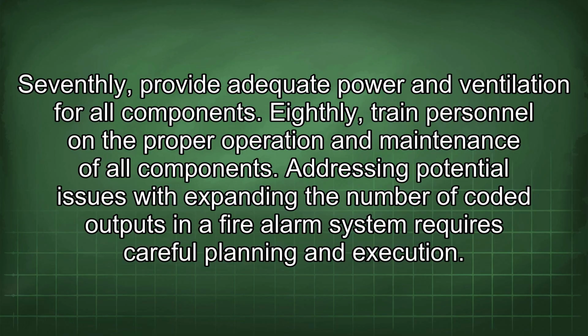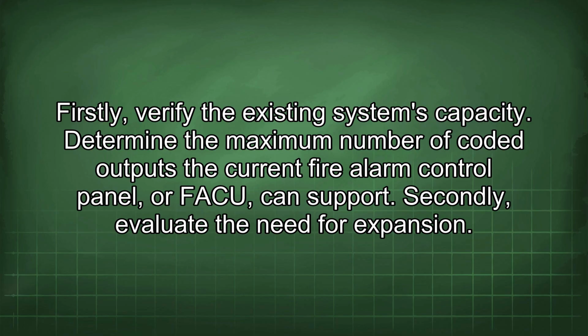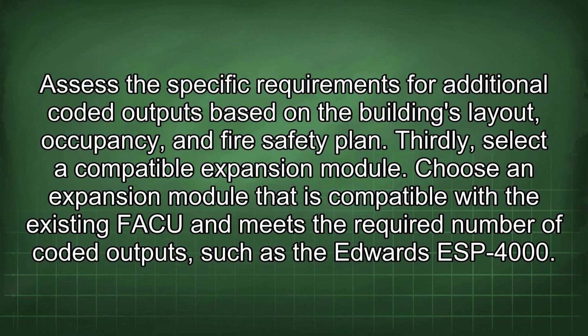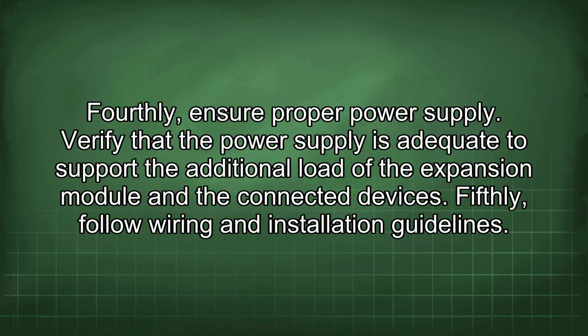Addressing potential issues with expanding the number of coded outputs in a fire alarm system requires careful planning and execution. Firstly, verify the existing system's capacity: determine the maximum number of coded outputs the current fire alarm control panel, or FACP, can support. Secondly, evaluate the need for expansion: assess the specific requirements for additional coded outputs based on the building's layout, occupancy, and fire safety plan. Thirdly, select a compatible expansion module: choose an expansion module that is compatible with the existing FACP and meets the required number of coded outputs, such as the Edwards ESP-4000.